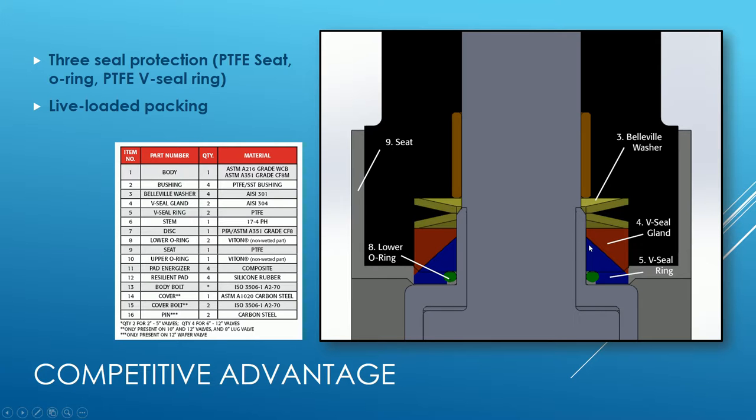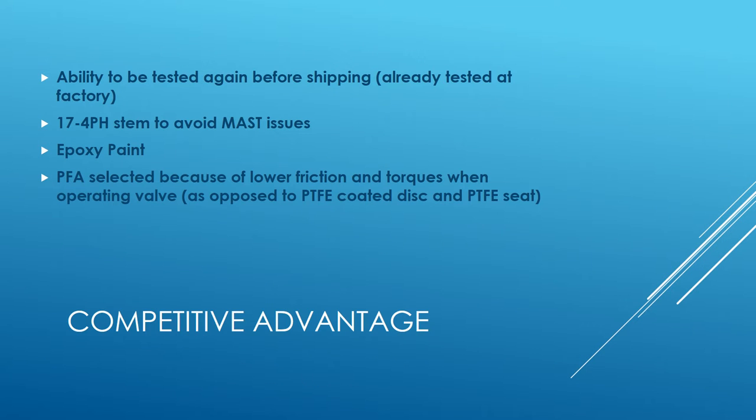If media gets past the seat, it will run into the O-ring, and after the O-ring you have a V-seal ring — so you have three layers of protection. The live loaded packing uses Belleville washers that will self-adjust for the life of the valve, ensuring good, consistent pressure on the sealing.